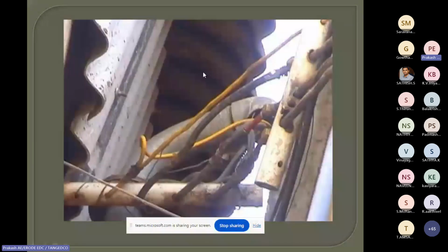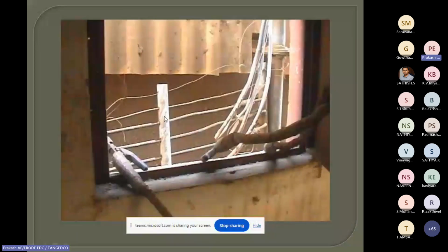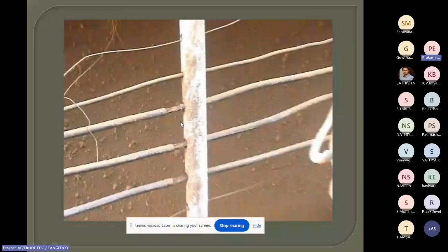This is the tampering where they have done it. Here you can see the tamper - this is a bare conductor. They removed the seal from it and are tampering it. You can see here clearly, this is a line where they have cut down the sleeve, removed it, and from the bare conductor made a hook.